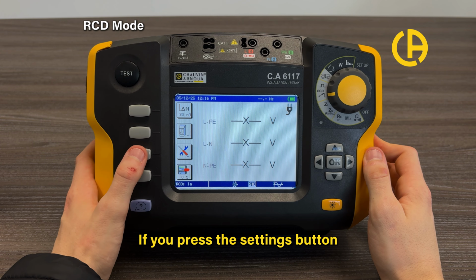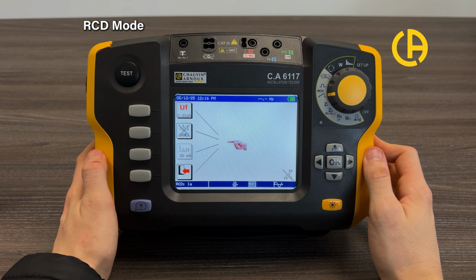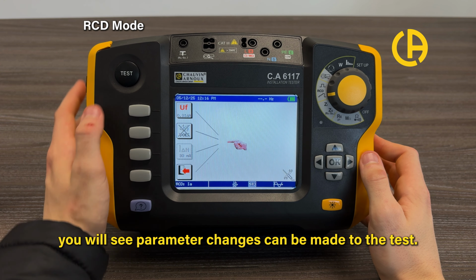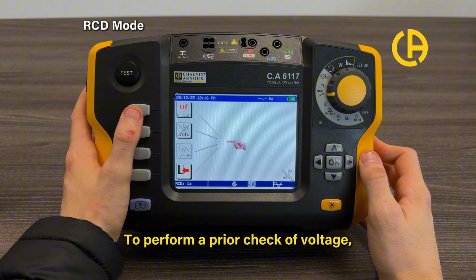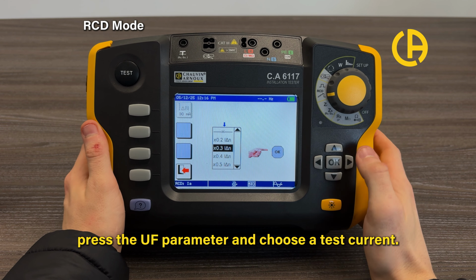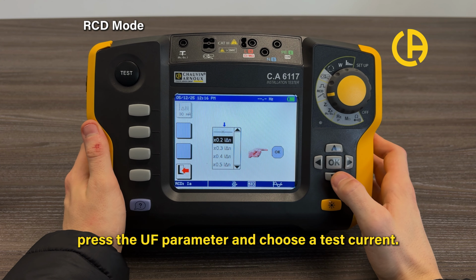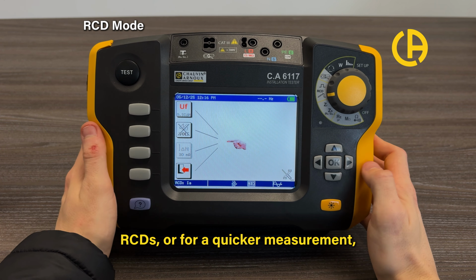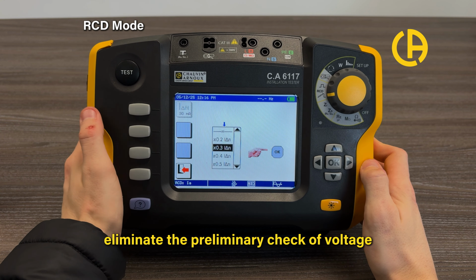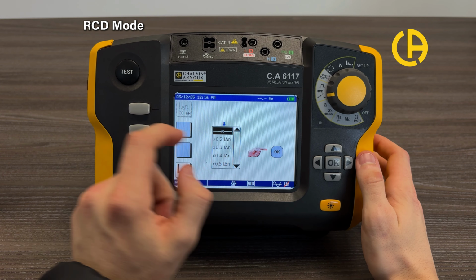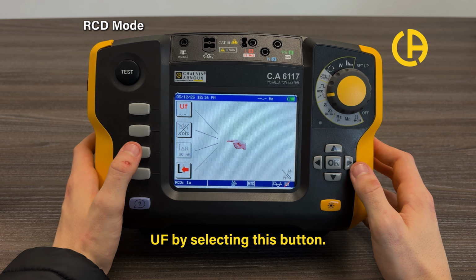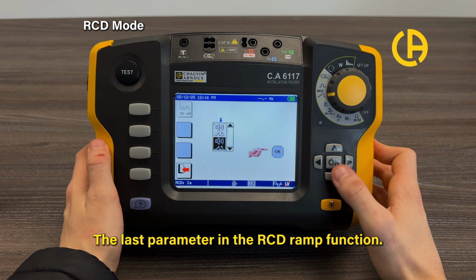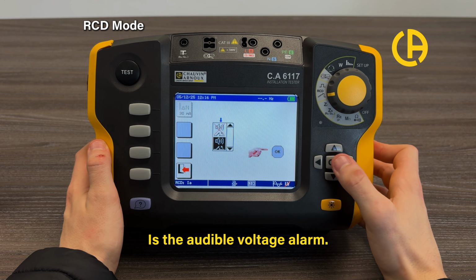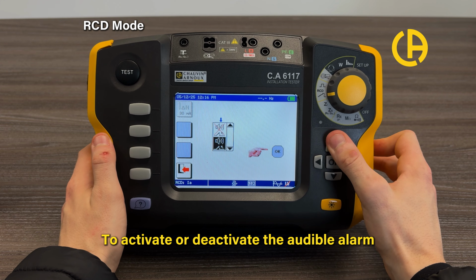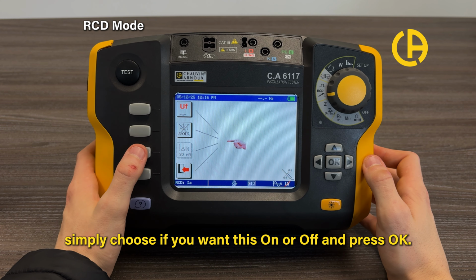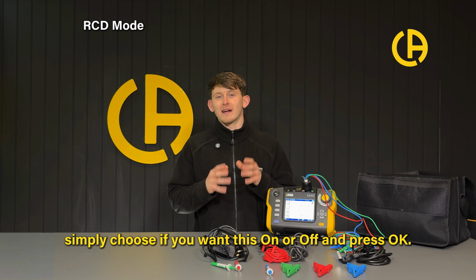If you press the settings button in the RCD ramp mode function, you will see parameter changes can be made to the test. To perform a prior check of voltage, press the UF parameter and choose a test current. For type EV RCDs or for a quicker measurement, eliminate the preliminary check of voltage UF by selecting this button. The last parameter in the RCD ramp function is the audible voltage alarm. To activate or deactivate the audible alarm, simply choose if you want this on or off and press OK.